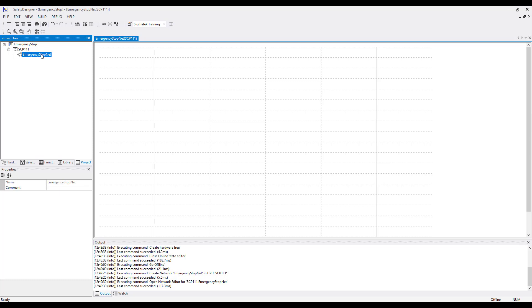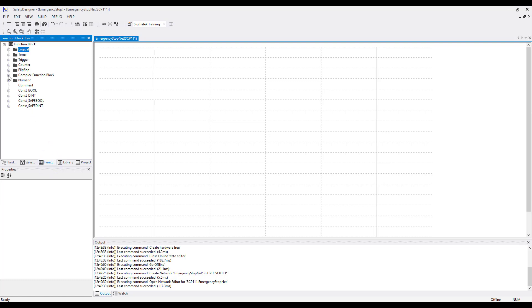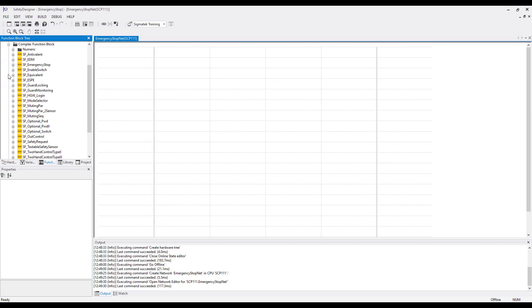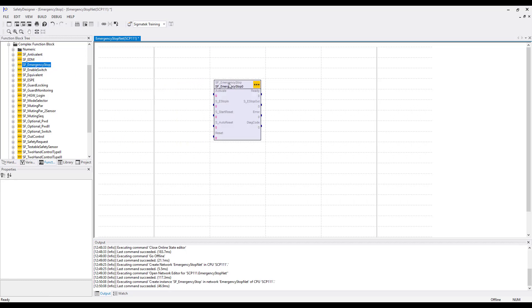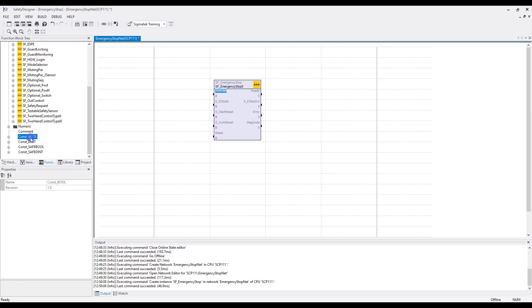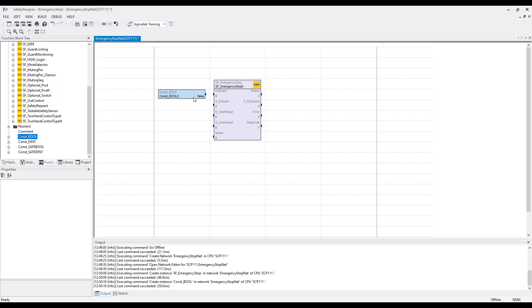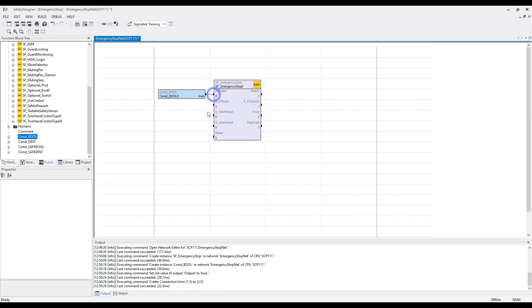We need a function block for the emergency stop. Go to the function block tree and open the folder Complex Function Blocks. In the folder there is the block SF_Emergency Stop. Put this with drag and drop onto the network. The emergency stop has an Activate input. For this we use the Const_BOOL from the function blocks — put it with drag and drop on the network. Set the Const_BOOL to True to set it permanently active.